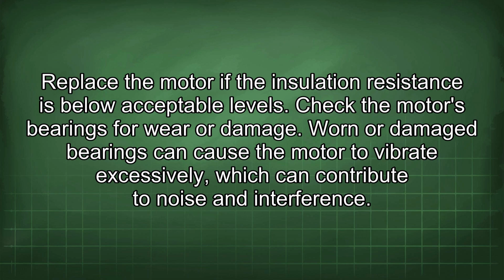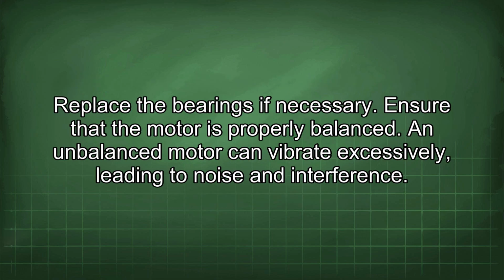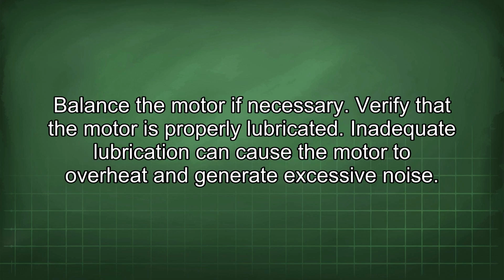Check the motor's bearings for wear or damage. Worn or damaged bearings can cause the motor to vibrate excessively, which can contribute to noise and interference. Replace the bearings if necessary. Ensure that the motor is properly balanced. An unbalanced motor can vibrate excessively, leading to noise and interference. Balance the motor if necessary.